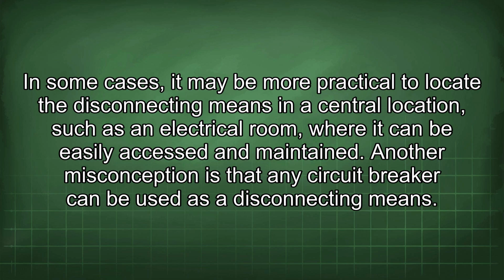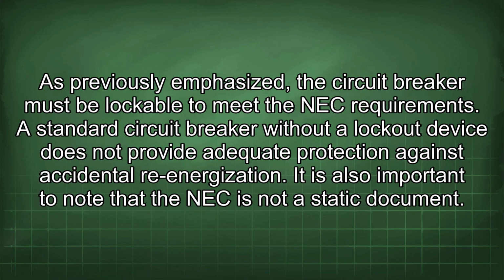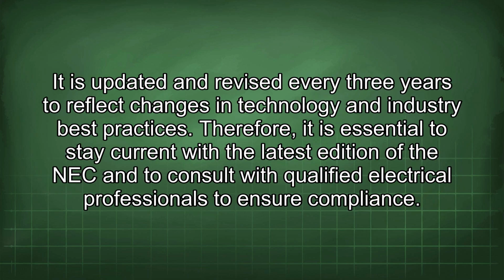Another misconception is that any circuit breaker can be used as a disconnecting means. As previously emphasized, the circuit breaker must be lockable to meet the NEC requirements. A standard circuit breaker without a lockout device does not provide adequate protection against accidental re-energization. It is also important to note that the NEC is not a static document. It is updated and revised every 3 years to reflect changes in technology and industry best practices.